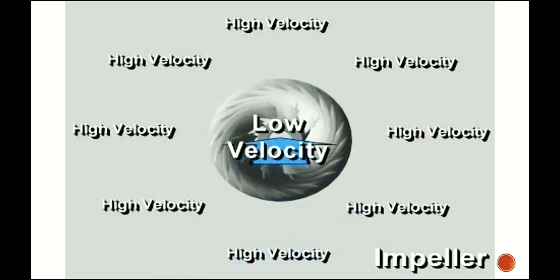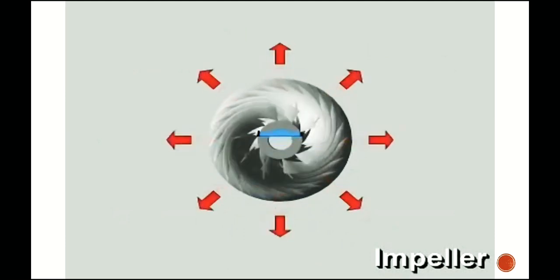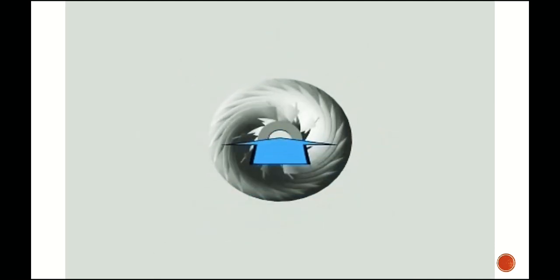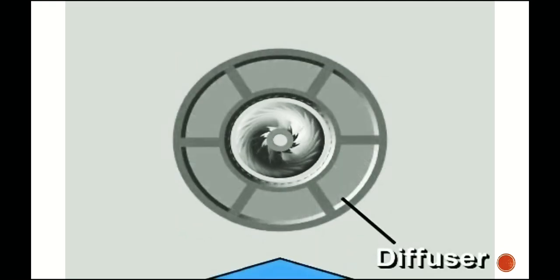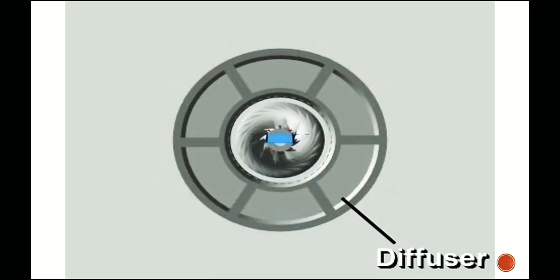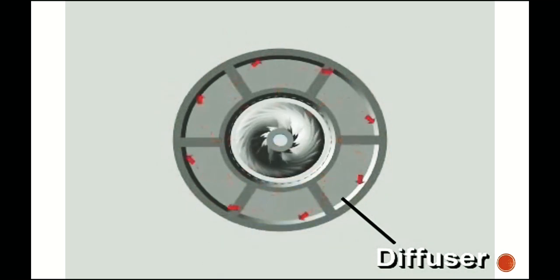The impeller transfers its rotational energy to the vapor, but high velocity does not equate to high static pressure. To achieve the desired pressure increase or compression, the vapor must be slowed down, converting its velocity pressure to static pressure. That is where the diffuser comes in. As high-velocity vapor moves radially outward through the diffuser, the flow area increases, slowing the vapor and increasing the static pressure. Some models have diffusers with vanes or pipes which change flow direction and further slow the vapor.